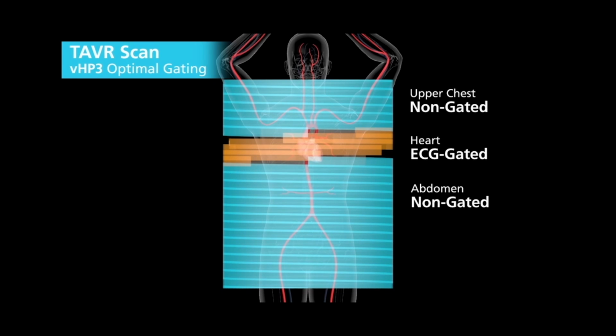With VHP3, up to three separate scans with three different IQ requirements can be combined into a single scan. For example, a non-gated upper chest followed by a gated heart and a non-gated abdomen can be accomplished in a single run, with the scanner adjusting pitch and dose in each scan section.